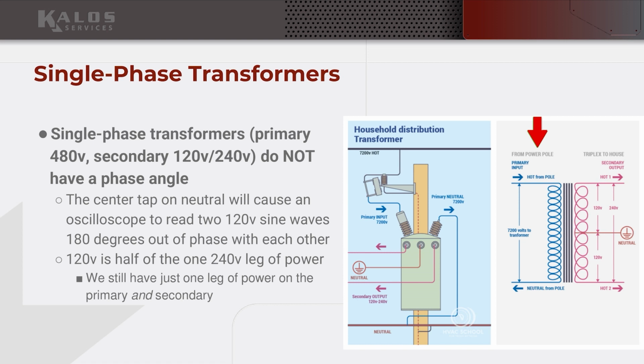Now if we look at our primary, that's pretty clear how this can be single phase when we look at the primary side. The confusion comes into play when we look at the secondary side. But the secondary side is also just one coil. Let's forget about the neutral for a second. We have one coil on our secondary side, which has an inductive or flux linkage with that primary side of one coil.